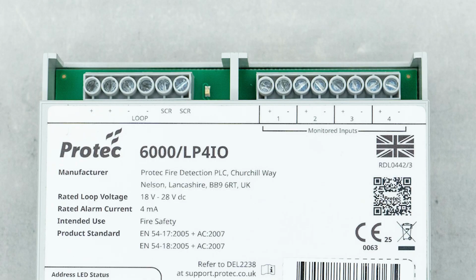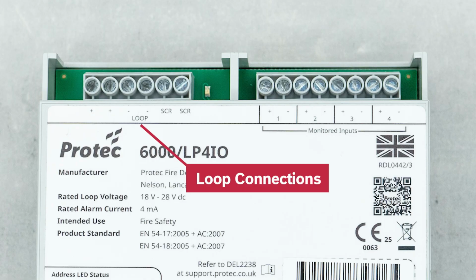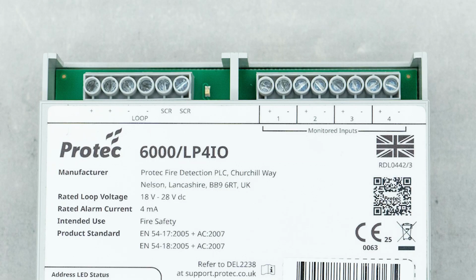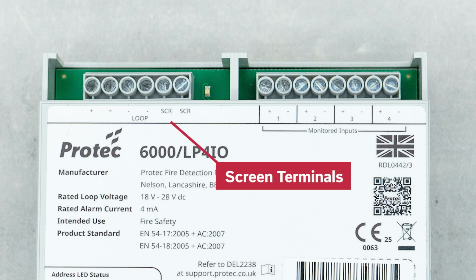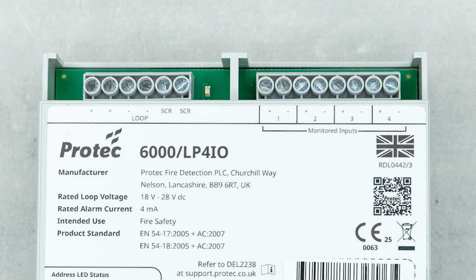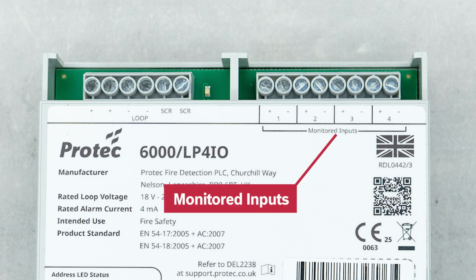Now we're going to take a look at the hardware on the LP4IO. Starting up at the top on the left hand side, we've got our loop connections. There are 2 positives and 2 negatives, that's the input and the output for the loop, and then of course we've got 2 dedicated screen terminals as well. After that we've got 4 monitored inputs. These are monitored using a 47k ohm resistive end of line.